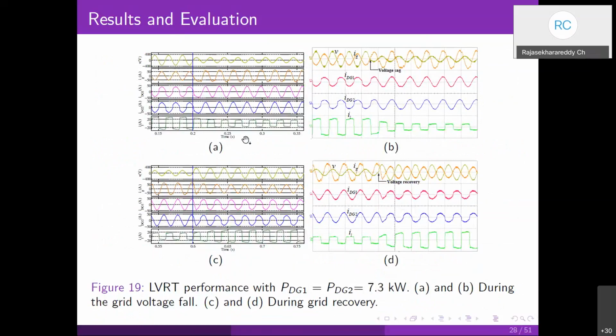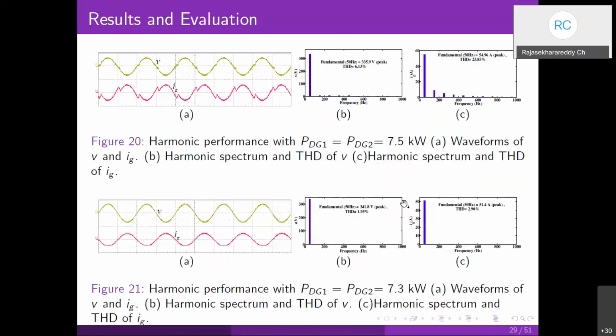Same as the case with a single DG inverter. Now we see the low voltage ride through performance. You can see we have a voltage sag occurring. As the voltage sag happens, the inverters reduce the active power generation and start to inject reactive current into the grid to aid grid recovery. Once the grid recovers from this voltage sag or fault, the inverter goes back to the normal mode of operation, and you can also see the smooth transition between LVRT mode and normal mode of operation. That is about it.